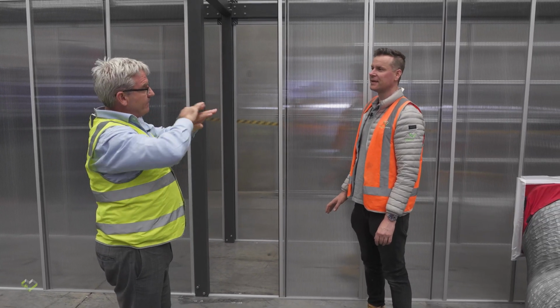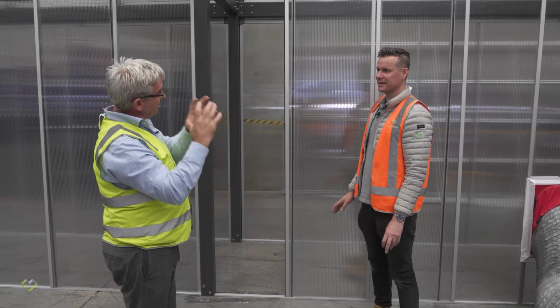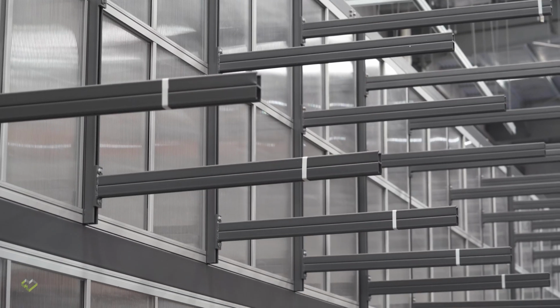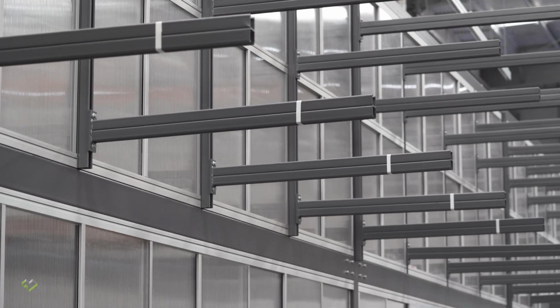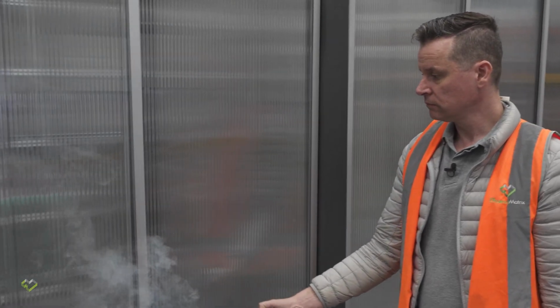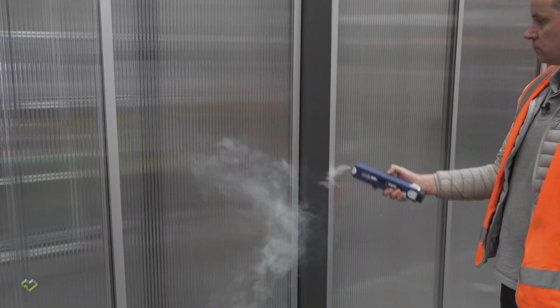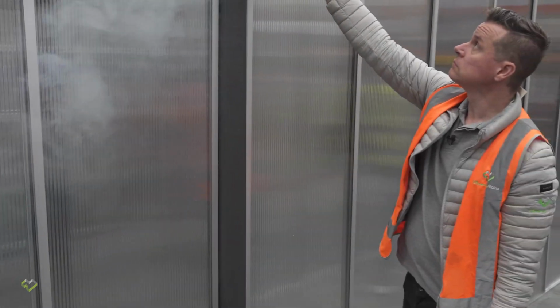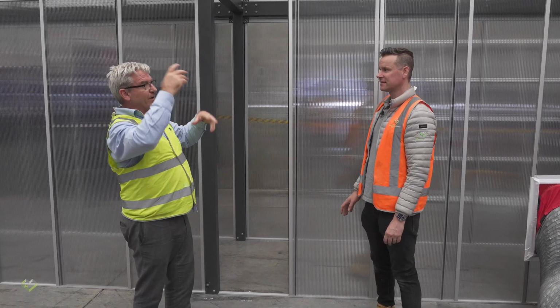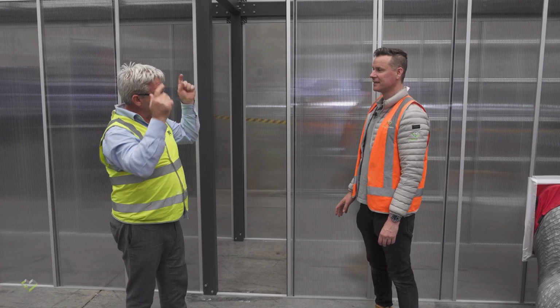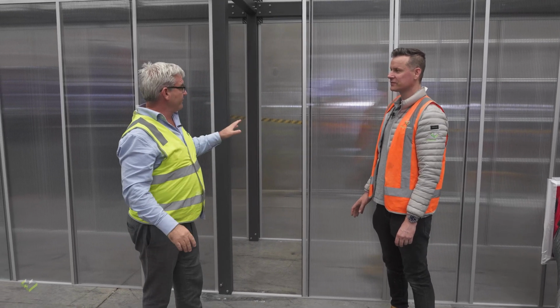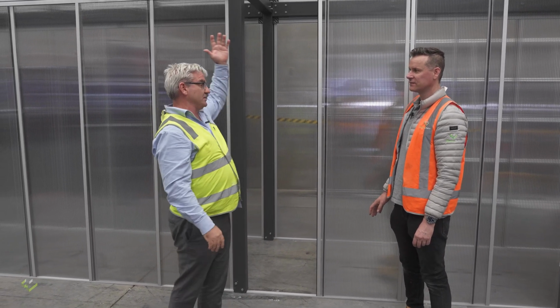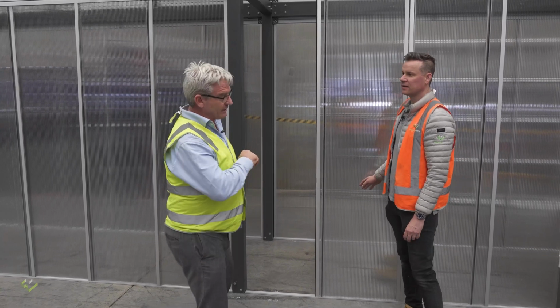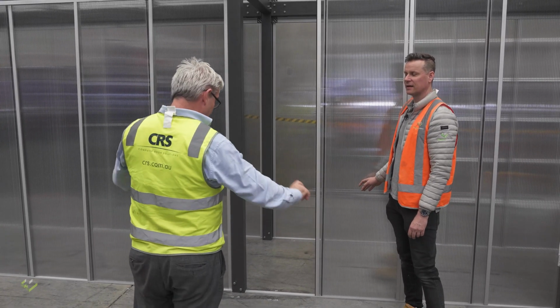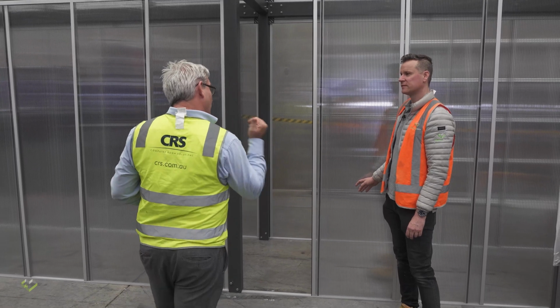So now we flip the lid, we make it as sealed as possible on top so there's no air pockets. So you have basically a box, so there's no air pockets on the sides or at the top. So you want air as clean as possible to go through that rectangle, in and out. None of these pockets of air getting trapped on raised lids and cavities of metal brackets and so forth. So very critical you get the air in and get it out as efficiently as you can. And getting back to it, having all your brush blanks on the side, having all your panels in, so it's a box, one way only.